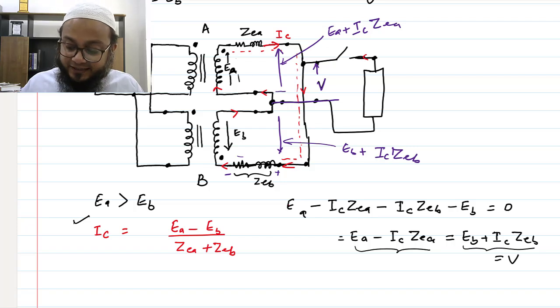And how does it affect this? This circulating current will force the voltage which is higher, the terminal voltage of that transformer, to be lower. And for the transformer whose induced voltage is lower, it will add up the voltage there, and that's how it will compensate.